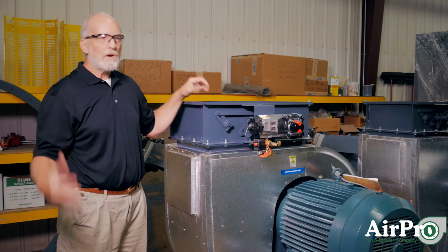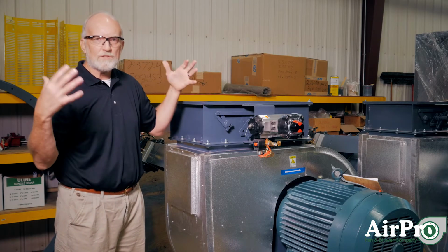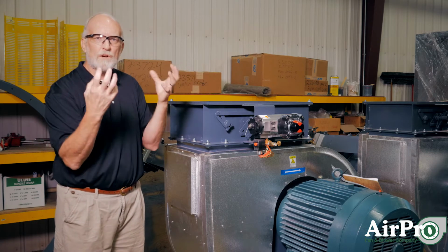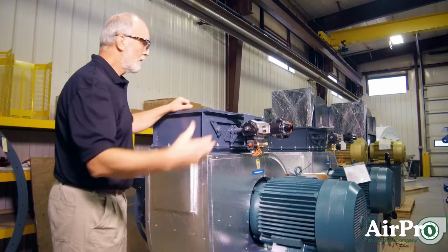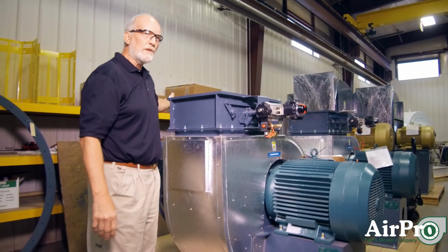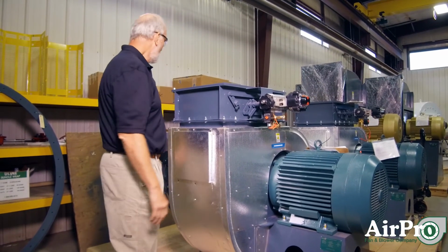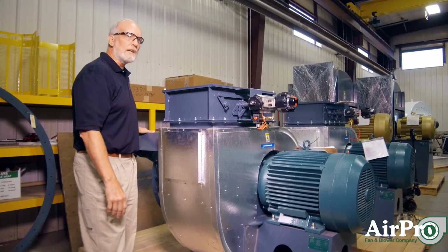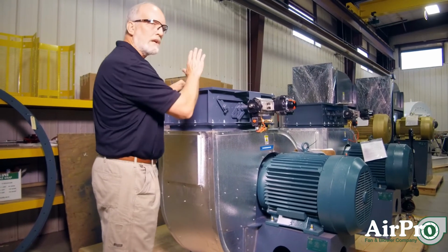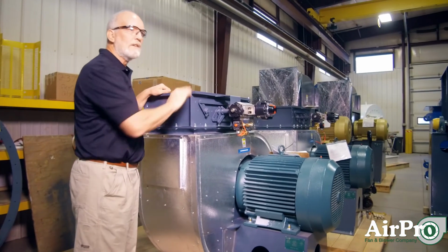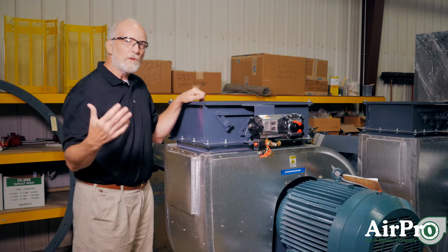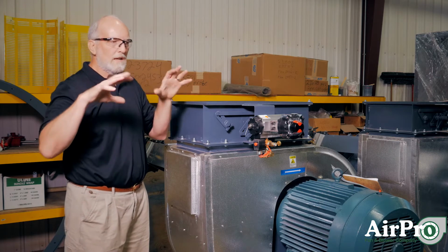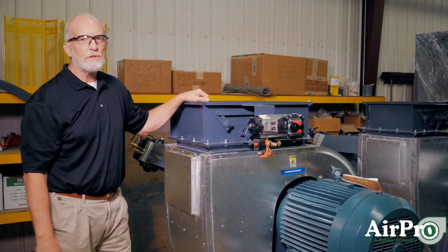In a power plant, turbines generate a lot of exhaust that's contaminated and very high temperature. So we bring fresh air in through a filter box and through a silencer. We regulate that flow with the inlet vane damper here, and we can also balance it with the outlet damper here. By regulating the incoming flow, we're able to maintain cooling for the turbine exhaust.